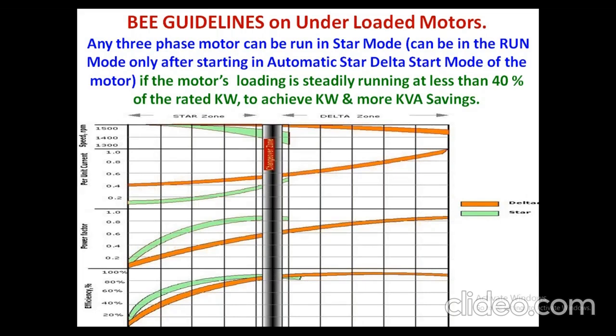It depends upon the motor application, whether it's a constant torque or a variable torque, and based on the application, the energy savings is possible for a given motor. This is a BEE table. BEE is a guideline table. It's an excellent table. You always situate the motor in the zone between 60 to 80% for healthy running of the motor. The motor loading decides the motor efficiency. That is, the motor running losses also can be curtailed if the motor loading is maintained at 60 to 80% for any given motor.